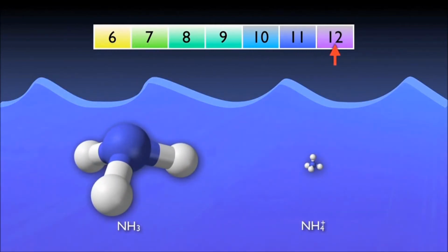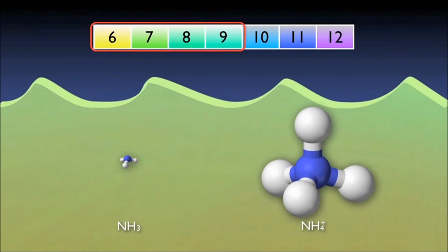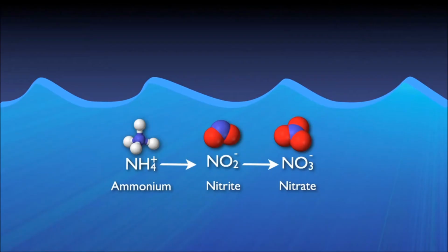Since wastewater typically ranges between a pH of 6 and 9, almost all of the ammonia will be in the ionic form. Since ammonia testing accounts for both forms, ionic and gaseous, it is not necessary to worry about each form separately. No bacteria is necessary for this conversion, it just happens. The next step in the process consists of converting ammonium to nitrite and then nitrate. This two-step process is usually lumped into one term, nitrification.